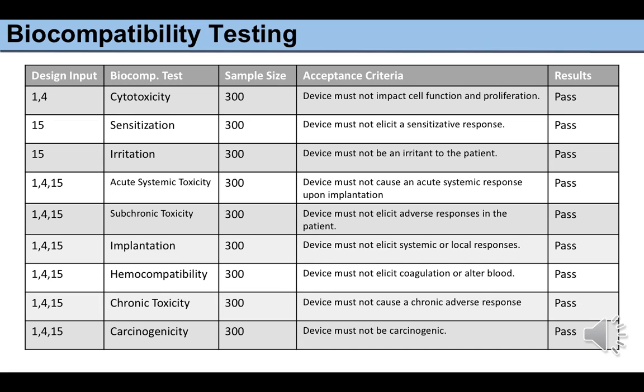For hemocompatibility, the device was tested for hemolysis, complement activation, and thrombogenicity. For chronic toxicity, the device was implanted in mammalian cell culture and larger animal models to determine the likelihood for toxicity that would be extremely detrimental to patient health. Further, for carcinogenicity, we wanted to quantify the total amount of extractables and leachables using analytical chemistry methods with the appropriate sensitivity to determine whether or not our product was sound for biocompatibility. All of these tests passed.